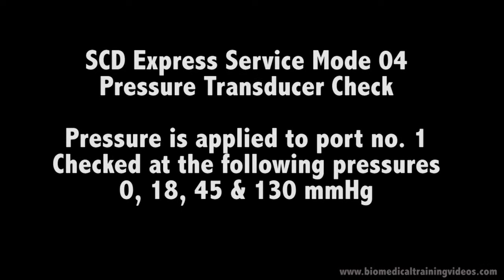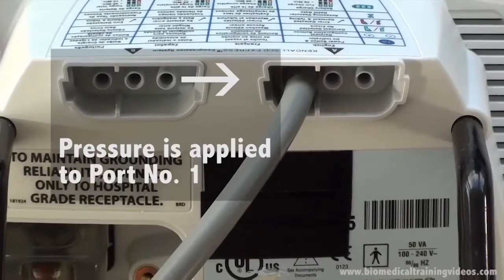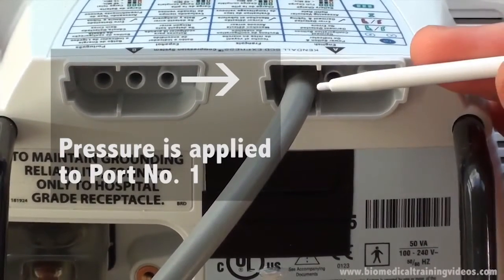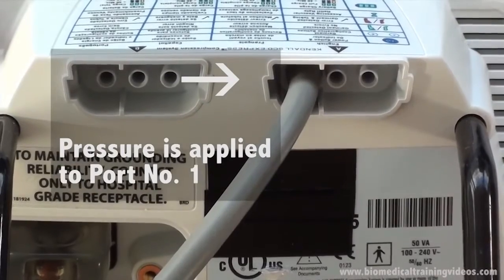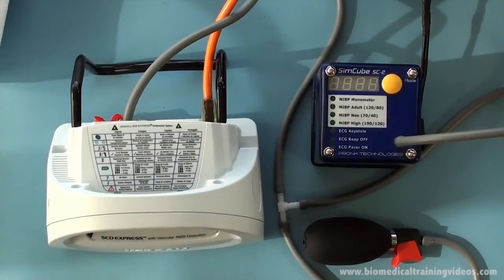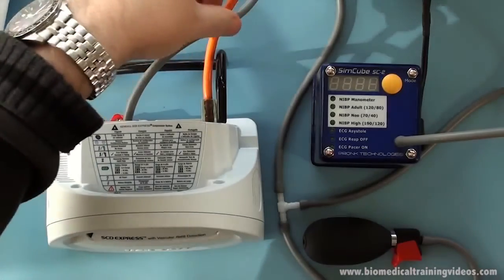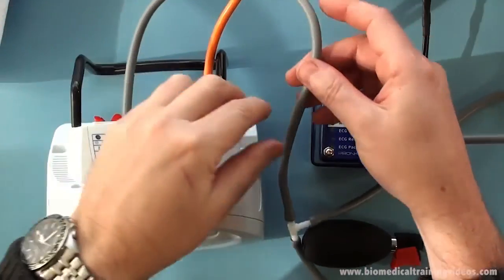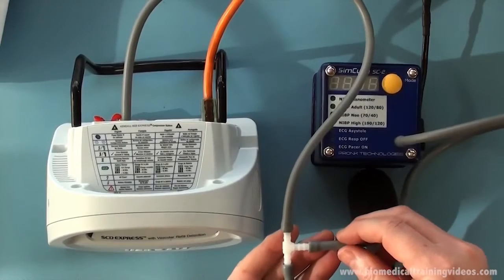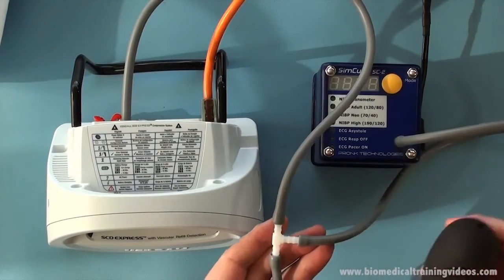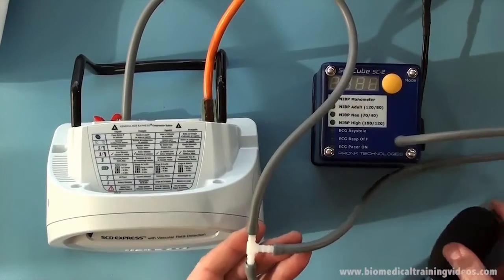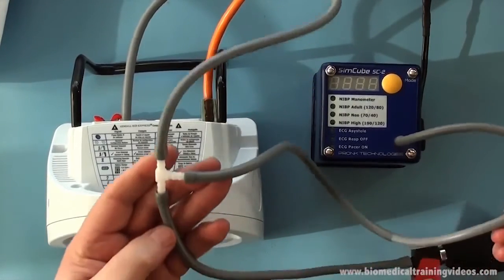So test mode 04 is the pressure calibration check. In this case we apply pressure to the port that I'm pointing to there, which is connected to the pressure transducer internally. The test jig is just a cable, T-piece, something to generate some pressure. I'm just using a bulb and a manometer to measure the pressure. It's a fairly simple setup procedure.